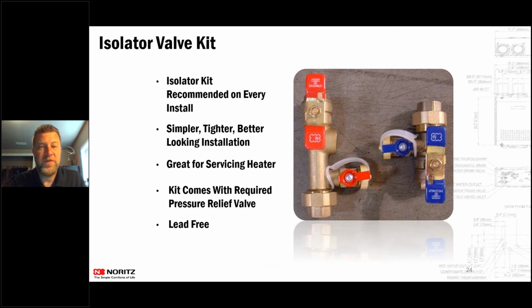So with some of our units, they come with isolation valves. Some of the units don't come with isolation valves, but isolation valves are something that we highly recommend be installed on every single install that is put out there. With the isolation valve, it does come with the pressure valve that is required for the install. It's a pressure relief valve. It's 150 PSI. It actually screws right in here on the hot side of that isolation valve.